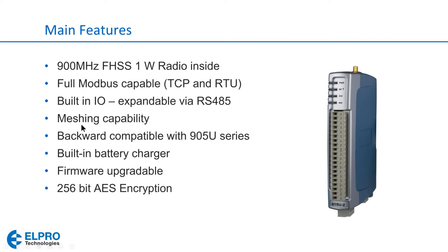The radio portion has meshing capability. Meshing refers to automatic repeater selection — if a normal direct path to a remote radio is lost, the radio will automatically figure out which repeaters to use to get the message to the final destination. These radios are also backward compatible with the 905U series, and are considered the second generation of that product.